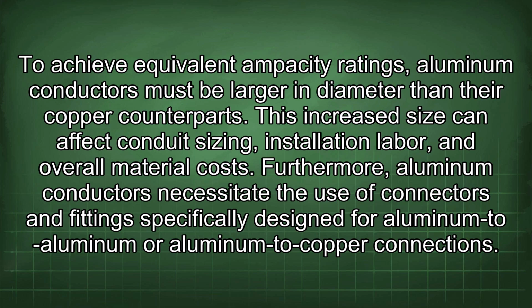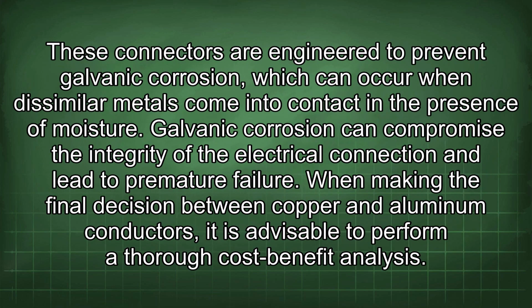Furthermore, aluminum conductors necessitate the use of connectors and fittings specifically designed for aluminum to aluminum or aluminum to copper connections. These connectors are engineered to prevent galvanic corrosion, which can occur when dissimilar metals come into contact in the presence of moisture. Galvanic corrosion can compromise the integrity of the electrical connection and lead to premature failure.